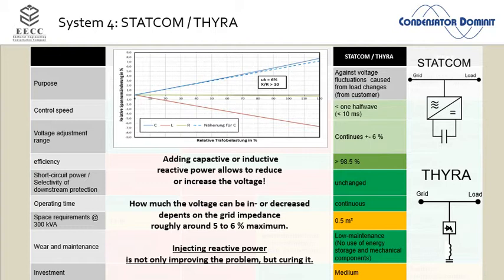That's a standard 1 MVA 6%, 1.25 MVA 6%. Those are typical sizes. In housing areas it's maybe smaller transformers, but in industry, 1 MVA is a typical size. So if I take 1 megawatt inductive load, that would be, for example, the startup of a big motor. If I start a big motor with 250 kVA or 300 kVA direct online, then I might have 1 megawatt of inductive load and about 100 kilowatt real power.